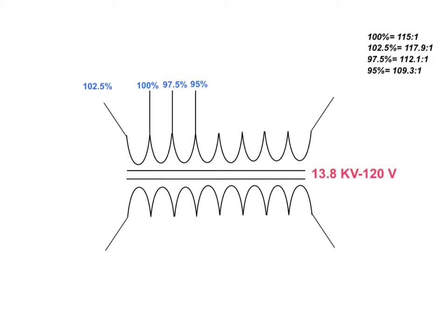Now remember, when we're dealing with a multi-winding transformer, multi-tap on the top there, we are decreasing our number of turns for the most part. I know we have this guy here, but let's talk about these two here. As we decrease our number of turns and the voltage up here on our primary side is the same, we increase our volts per turn. And remember, volts per turn primary is equal to volts per turn secondary. So that's why we use these taps.